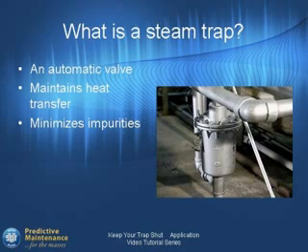Poor designs and failed components mean more steam is condensed back to water, wasting expensive heat energy. A steam trap is an automatic valve that opens to purge condensate and non-condensable gases from the system. The steam trap keeps steam pure and allows it to be repurposed. A steam trap is a vital component of the steam system that ensures efficient heat transfer while preventing impurities from corroding the rest of the steam system.